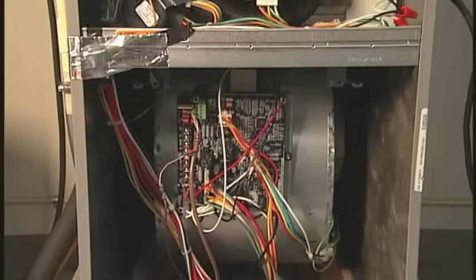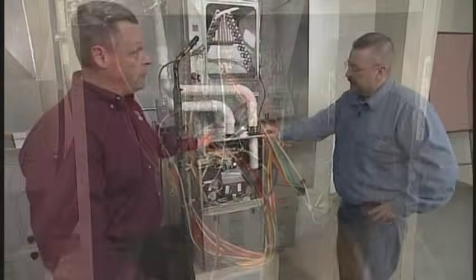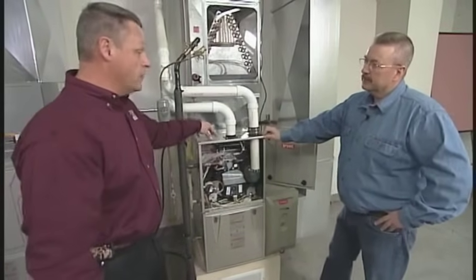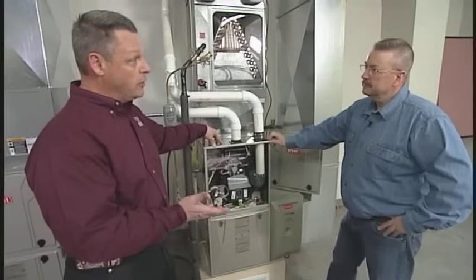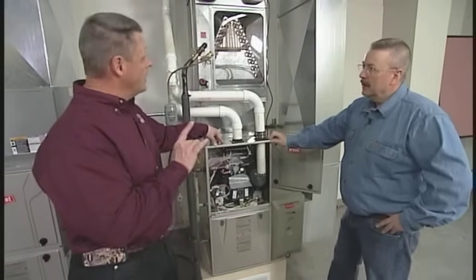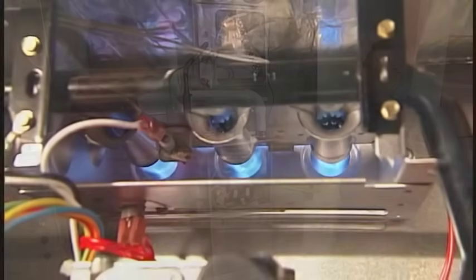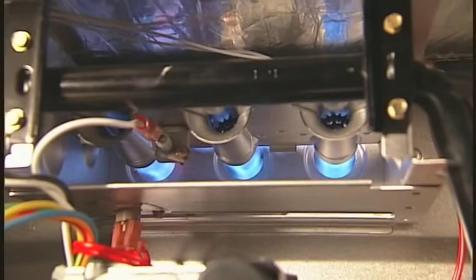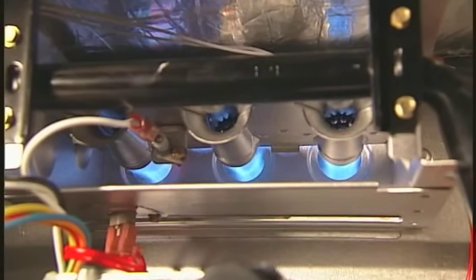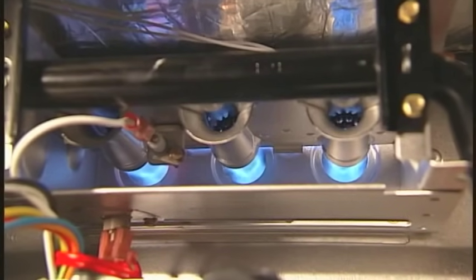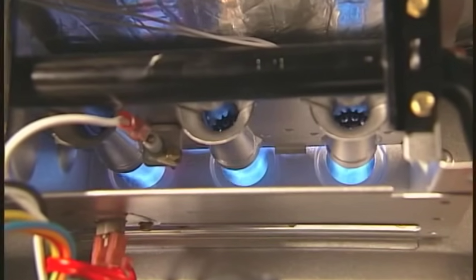And then we jump up to a modulating, which is 98% AFUE on the high end, which will give you full modulation from 40% firing rate all the way up to 100%. Again, we think about, we have to size the furnace for 100% heating load outside when it's 15 below. And that doesn't happen all that often, does it? Exactly. Majority of the winter, we're never at that level.